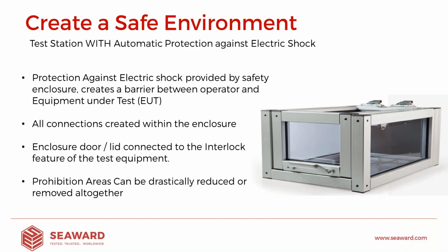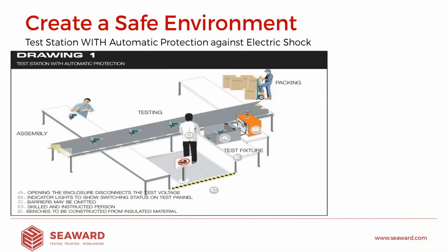So let's have a look at that in a production line environment. Here you'll see an ideal scenario for an item with a test enclosure. So let's point out the individual elements. We have here the test enclosure itself, in which the product is being tested. We have the test equipment. We have a beacon which would display when the area is live or unlocked or disconnected. You can see the benches constructed from insulating material, so that effectively if there was a problem, and if you do use any aluminium chassis for your frame, again, it's still insulated via the bench. There'll be rubber matting on the floor, again, just as a secondary level of protection for the operator.